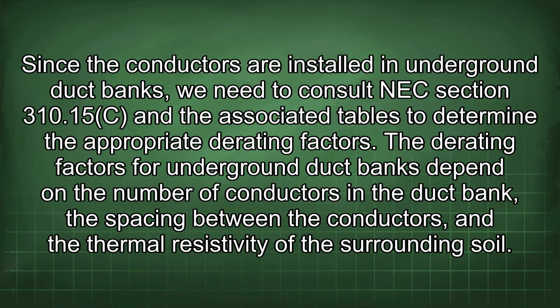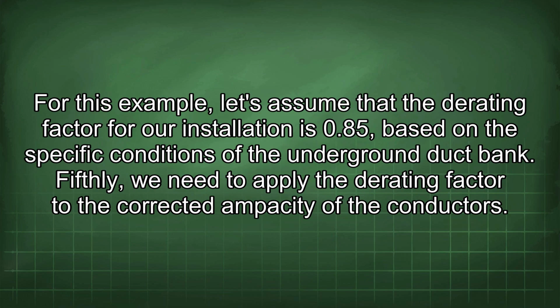Fourthly, we need to consider the derating factors for multiple conductors in a raceway. Since the conductors are installed in underground duct banks, we need to consult NEC Section 310.15(C) and the associated tables to determine the appropriate derating factors. The derating factors for underground duct banks depend on the number of conductors in the duct bank, the spacing between the conductors, and the thermal resistivity of the surrounding soil. For this example, let's assume that the derating factor for our installation is 0.85, based on the specific conditions of the underground duct bank. Fifthly, we need to apply the derating factor to the corrected ampacity of the conductors.